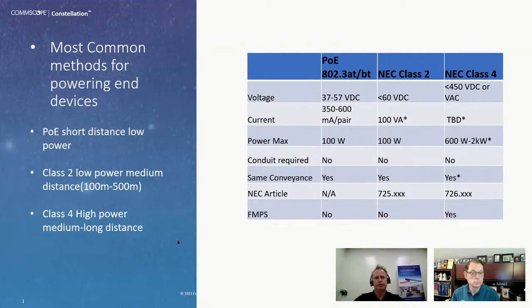NEC Class 4 is new, ratified last year in the NEC—it's Article 726 and all the sub-articles. In this situation, Class 4 power can typically deliver 600 watts at a minimum, and up to 2 kilowatts, perhaps more. It's really based on how many pairs are conducting power.